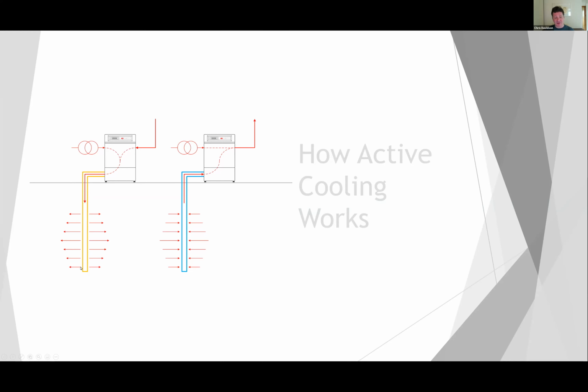So we're putting water into the ground, maybe 25, 30 degrees C, to push that heat back out into the ground. But it's a symmetrical process, except for the fact that in heating mode, the electrical energy consumed by the compressor helps you to heat, and in cooling mode, it actually hinders you. So you're actually rejecting extra heat because you're getting rid of that compressor energy into the ground as well.